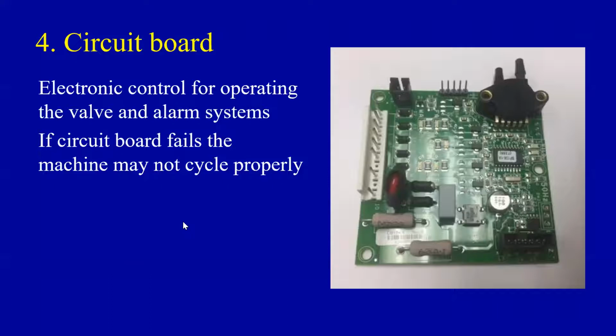Inside the concentrator, the fourth thing is the circuit board, or just a mini computer. This is one from the types of 10-liter concentrators that I said we bought for the pandemic. And it's a small computer inside, and biomedical technologists know about these computers. Health workers don't have to know anything, but just to know that if there's something wrong with the concentrator, then there are some lights in this circuit board that can go on, and they can tell you, for example, which valve it is, the valve before the cylinders or after the cylinders that's wrong, and some lights come on to tell you that. It's quite a clever computer, which a trained biomedical technologist can look at and say where the problem is within the concentrator.